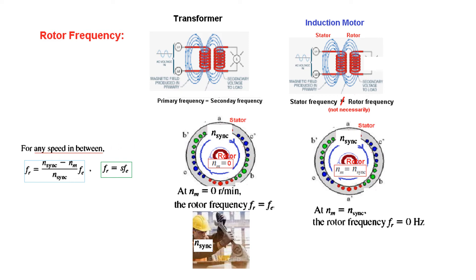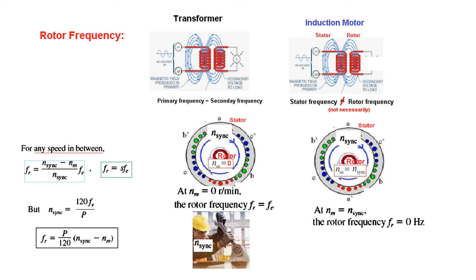For any speed in between, the rotor frequency is given by: F-r equals (N-sync minus N-m) divided by N-sync, multiplied by F-e, where F-e is the stator or supply frequency. This can also be written as F-r equals s times F-e, where s is the slip. Additionally, since N-sync is given by 120·F-e / P, we can derive another formula: F-r equals P divided by 120, multiplied by (N-sync minus N-m). We will use this formula in the problem solving.